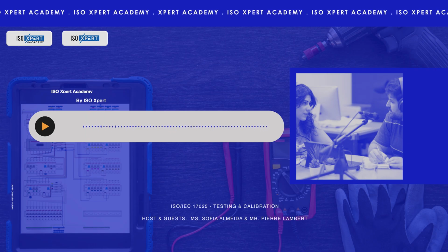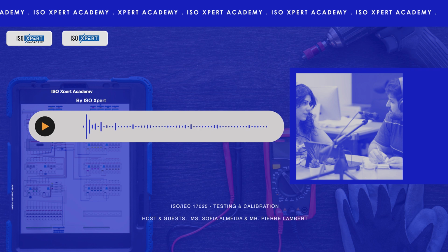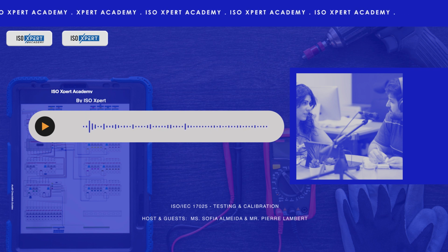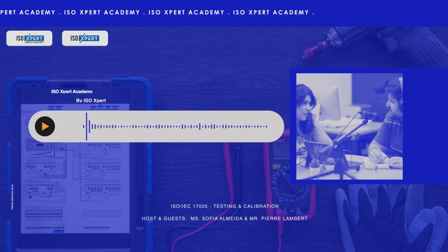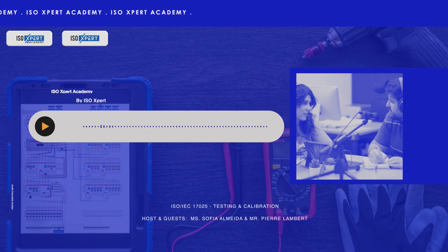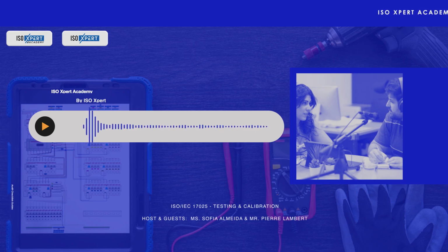Definitely. They'd expect to see evidence like detailed complaint registers tracking customer issues. They'd look for nonconformity reports or NCRs. NCRs. Yeah, documents that record the specific deviation, what went wrong, and then, often linked to that, corrective action requests, CARs. Which do what? They outline how the problem was investigated, what root cause was found, and what action was taken to fix it and prevent it from happening again. It's all about transparency, fixing mistakes, and crucially, learning from them for continuous improvement.